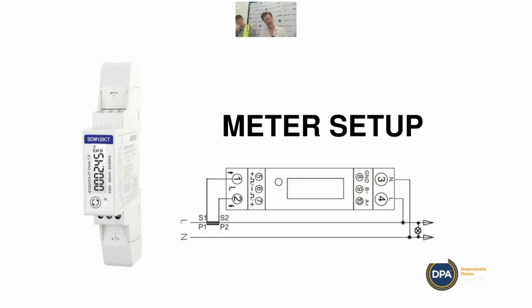Down the bottom here, we've got ports 1 and 2, which is where the CT is wired in. That's pretty straightforward. The main thing to know is that if the meter ends up facing the wrong direction, you don't have to get up to where the meter is to change it around, you can just swap these two cables to flip the direction.